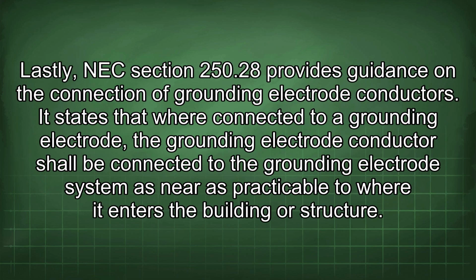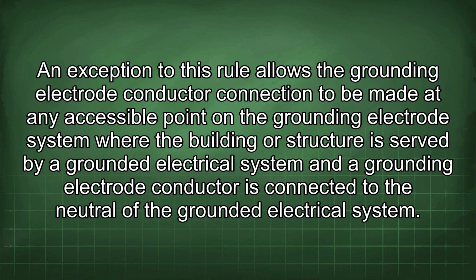Lastly, NEC Section 250.28 provides guidance on the connection of grounding electrode conductors. It states that where connected to a grounding electrode, the grounding electrode conductor shall be connected to the grounding electrode system as near as practicable to where it enters the building or structure. An exception to this rule allows the grounding electrode conductor connection to be made at any accessible point on the grounding electrode system where the building or structure is served by a grounded electrical system and a grounding electrode conductor is connected to the neutral of the grounded electrical system.